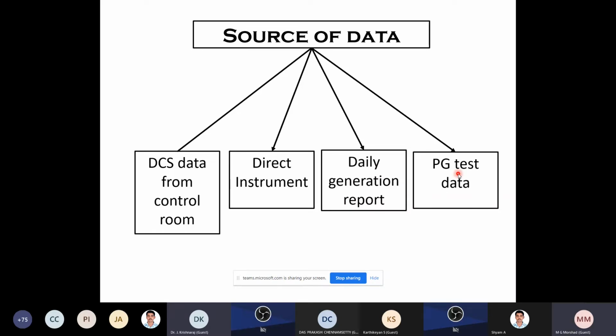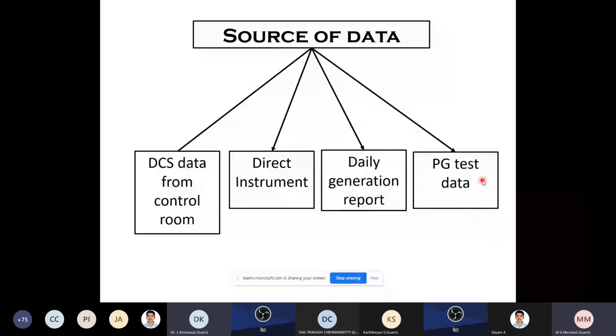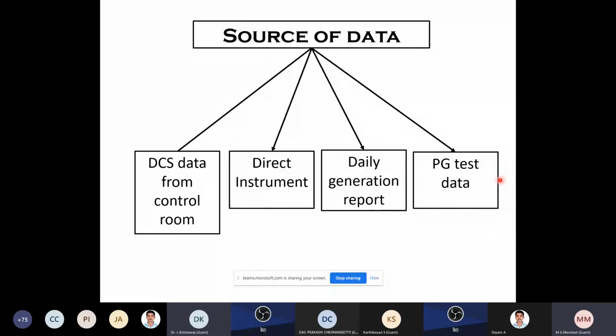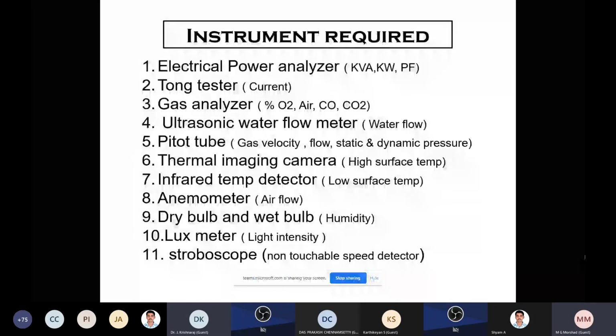And the PG test data: in all thermal plants, when a plant is starting, one PG test report will be prepared. If these data are not available, you can use this PG test data. But the PG test data should be the reference. So with reference to it, you have to take all these data. So whenever an energy audit team, internal or external, tries to do the energy audit in a thermal power plant, they have to fix the four data sources first. Only then will it be possible for them to get the exact data from the thermal power plant. Okay, now instruments required.